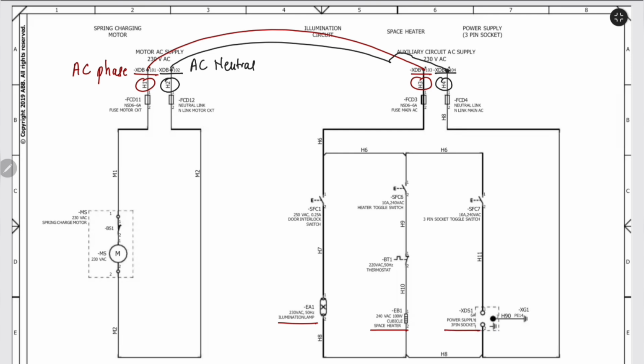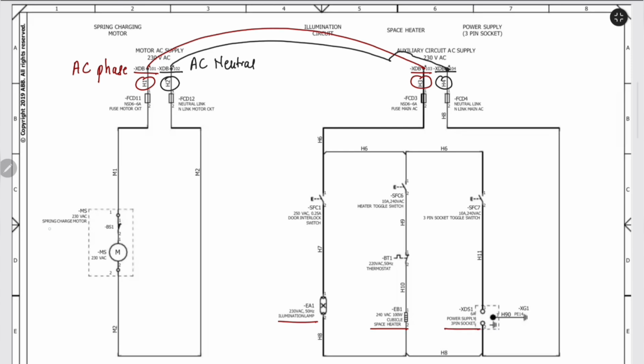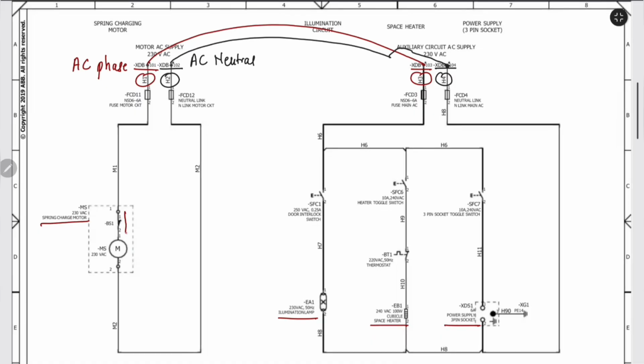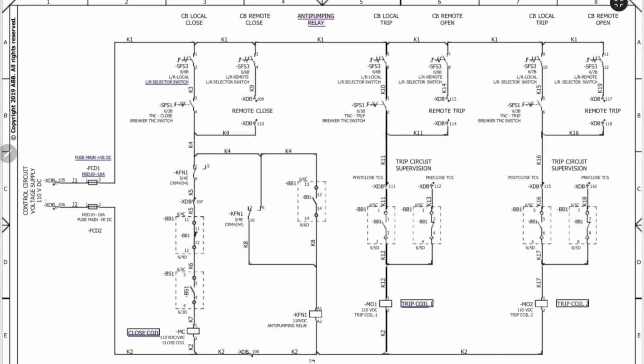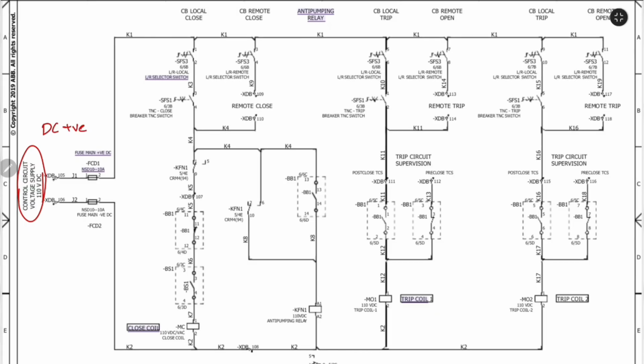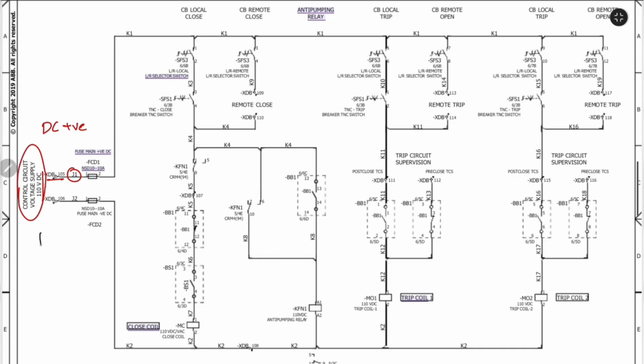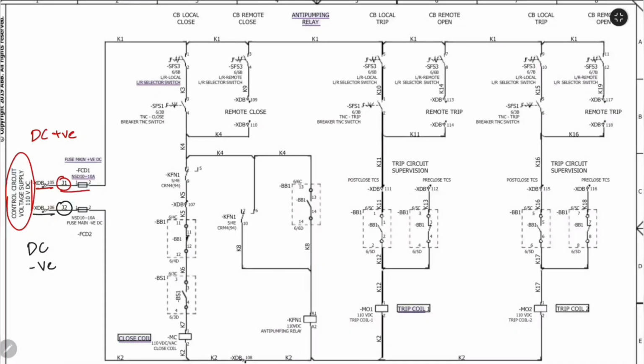As soon as the AC supply is switched on, the spring charging motor starts automatically through the limit switch and charges the breaker closing spring. Once the spring is fully charged, the motor automatically stops. Next comes the DC control supply, which is the backbone of the protection and control system. Connect the DC positive plus to terminal XDB105, J1. Connect the DC negative minus to terminal XDB106, J2. With both AC and DC supplies available, the breaker is now energized and ready for functional testing.